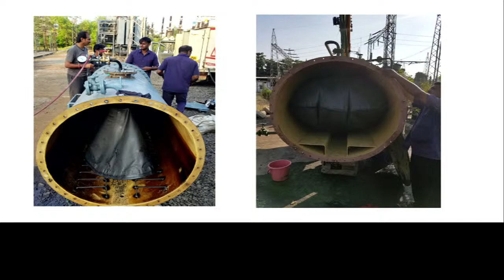Also the calibration of the MOG. Everyone says 1/3 oil is filled, 30% oil, but there is no calibration for it. So what I am suggesting to people is, calculate the volume of the conservator. If your conservator is around 5 kL, total oil capacity 5 kL, just fill 1/3 oil in it after draining, and see that you have calibrated. Otherwise there is no method.